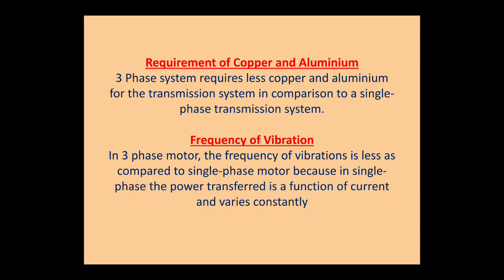In terms of frequency of vibration, three-phase motors have less vibration compared to single-phase motors. In a single-phase motor, power equals V × I × cos φ, so any variation in current directly varies the power. In a three-phase motor, power depends on line current as √3 × VL × IL × cos φ, and the effect of current variation is lesser, resulting in smoother operation.